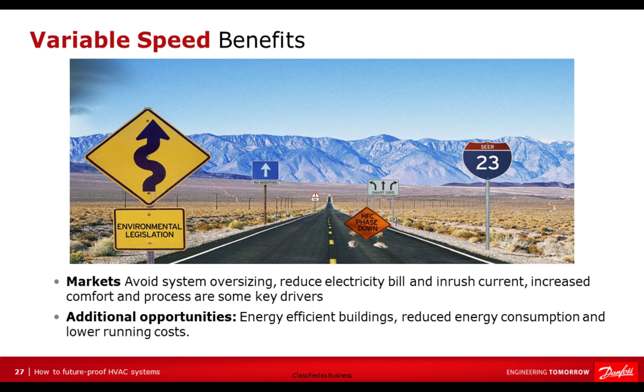Looking at a building profile, most of the buildings today are designed for the peak load, where they operate less than 5% of the time. While it's important to meet those max conditions, we must also consider the overall operating conditions of the building. Capacity modulation attenuates the power demand peaks, which also contributes to increasing the grid reliability and quality of the power supplied. Variable speed compressors also match the power input with the cooling capacity. The unit copes effectively with the changes in temperature and runs at partial load, which can also represent a 30% reduction in energy bill every year as compared to a fixed speed or mechanically modulated compressor. Stable temperature control also secures the process in an optimum way, providing better comfort, which also means energy efficiency in the buildings.